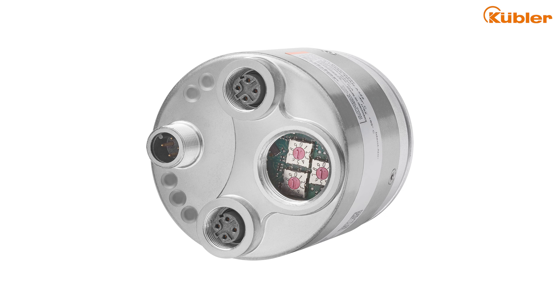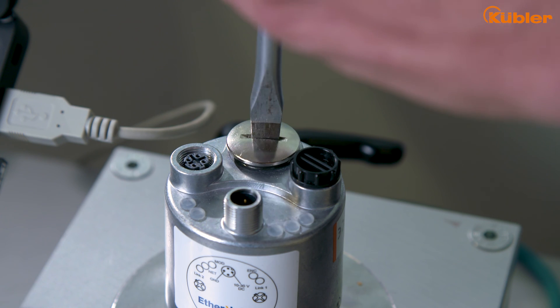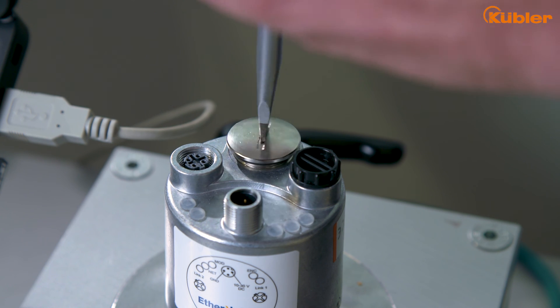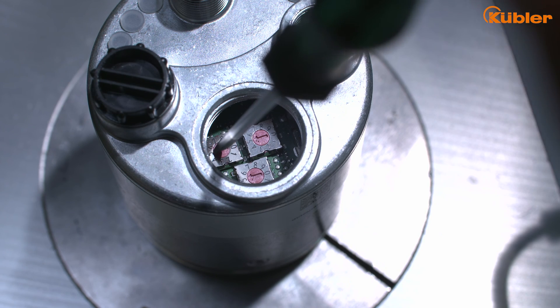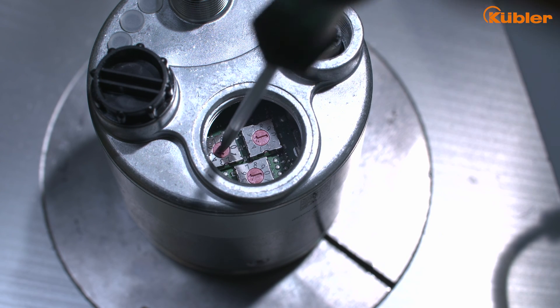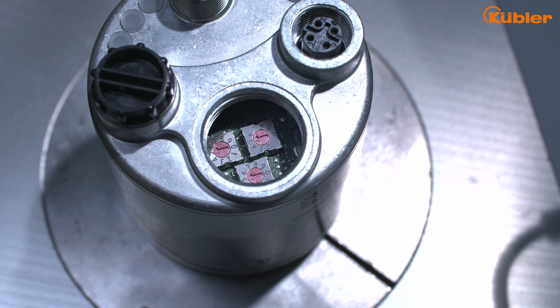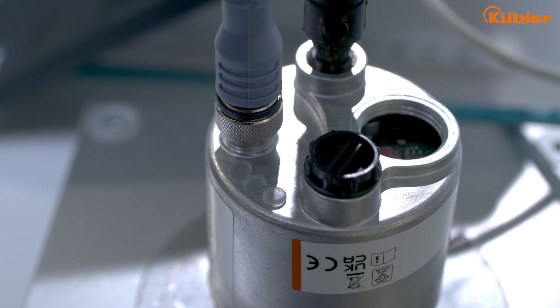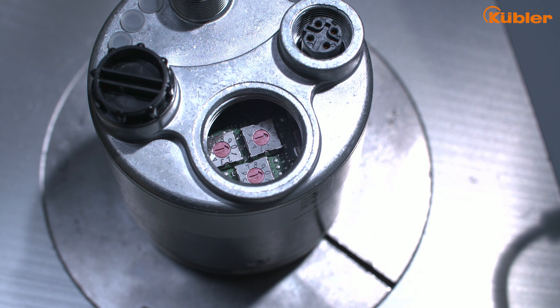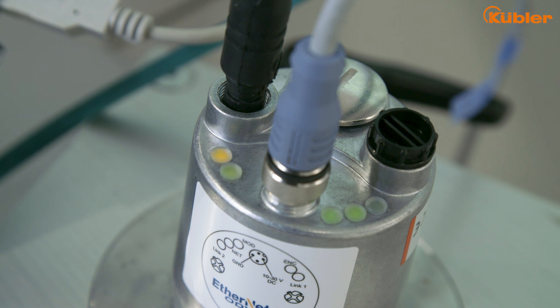A reset can easily be performed by setting the rotary switches on the back of the encoder to 555. To perform the reset, you can do the following procedure: Disconnect the encoder from the power supply. Set the rotary switches to 555. Connect the encoder to the power supply. Wait for approximately 5 seconds. Disconnect the encoder from the power supply again. Set the rotary switches to the position desired for operation, for example 000. Connect the encoder to the power supply. The encoder is now reset.